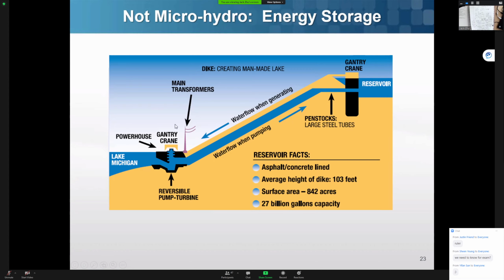But when the demand on the power grid is larger, so now you require more power on the power grid, then they will just let the water flow down to push the turbine. Now this part becomes a turbine generator. They're going to generate the energy to supply to the power grid. So it's a way to balance: when you have a lower demand, you use it as a pump to pump the water to a reservoir, kind of like storing the energy in there. When the demand on the grid becomes bigger, you let the water flow down to push the turbine. Now you have a generator station down there. You're going to generate the power to supply the grid demand.